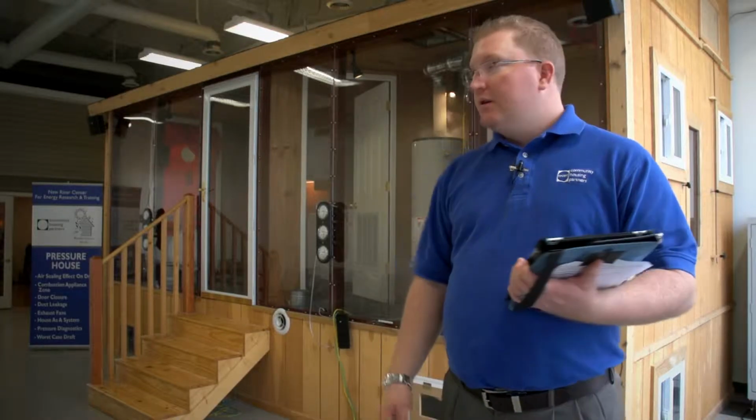The reason that happens is because now the supply air is not getting back to the conditioned space. Therefore, the return is having to pull air from other places to make up the amount of volume that it needs. So simply, one 6-inch flex line in the attic being knocked loose because of improper attachment and sealing is creating a health and safety issue in our home. Well, let's go inside now and walk through a basic CAZ test so that you don't have the same problems that Mike does.